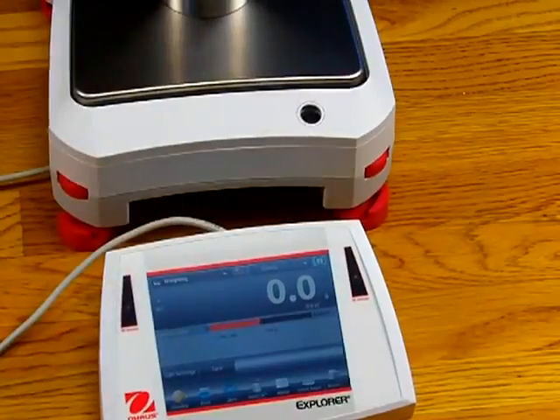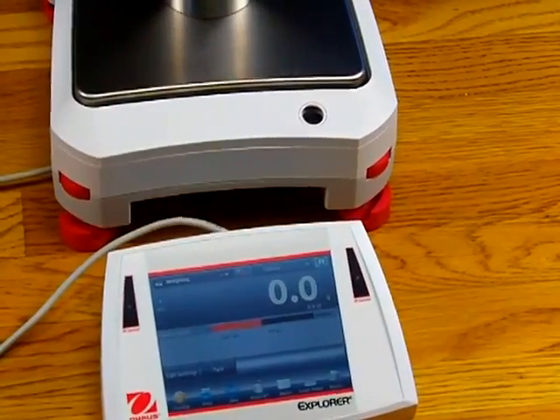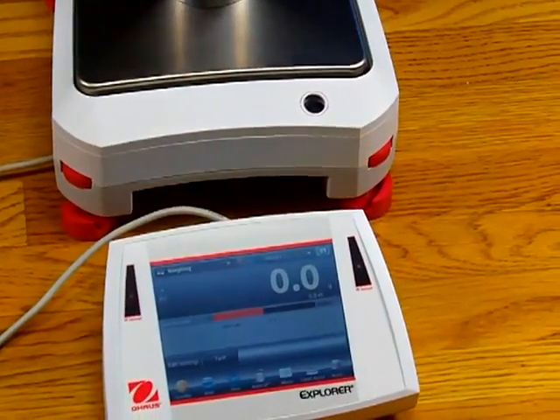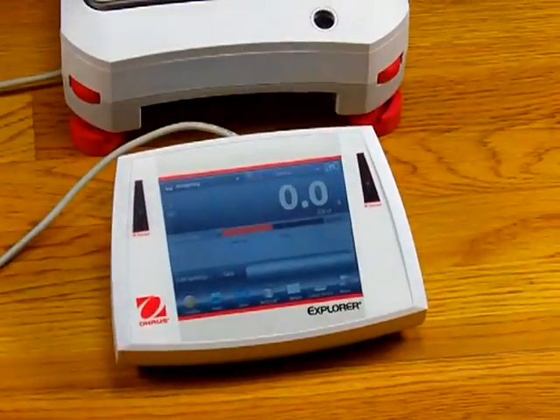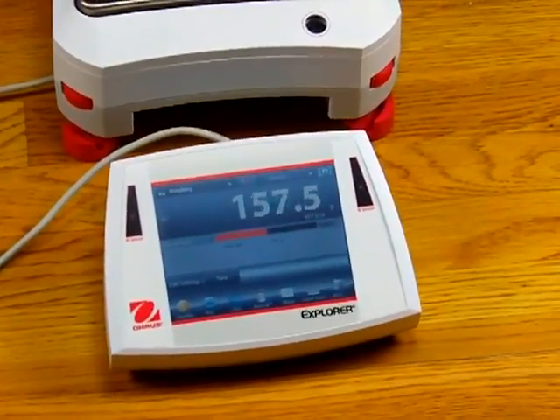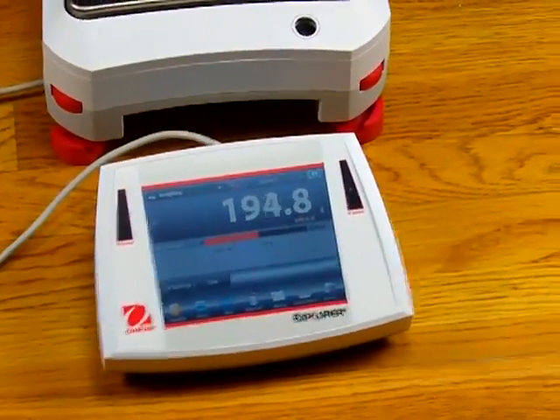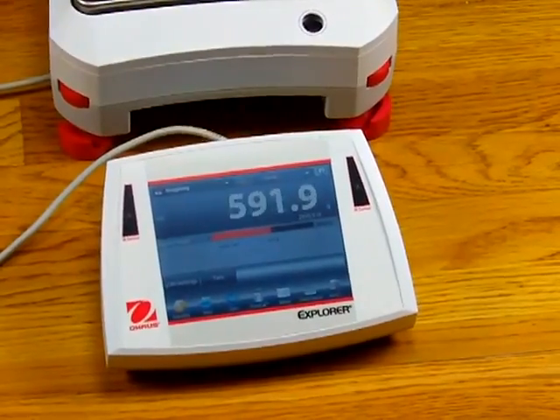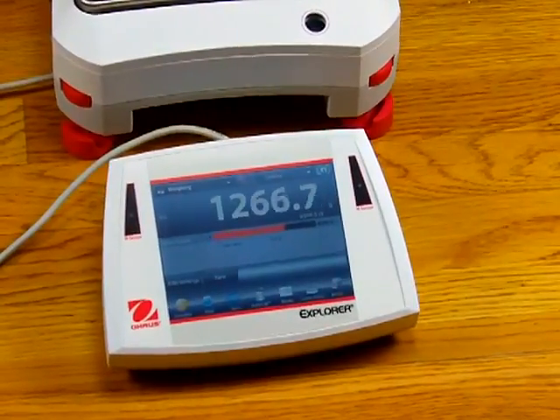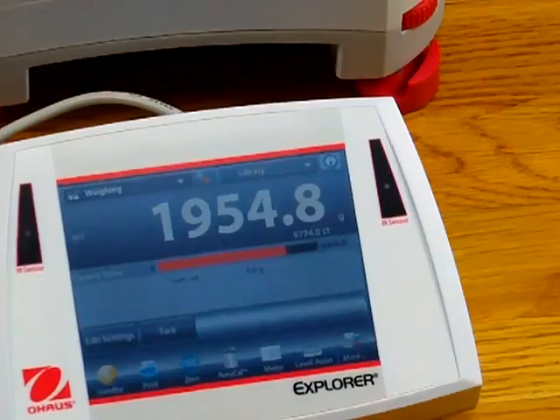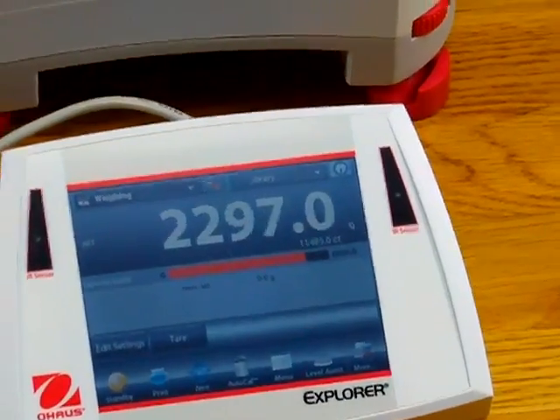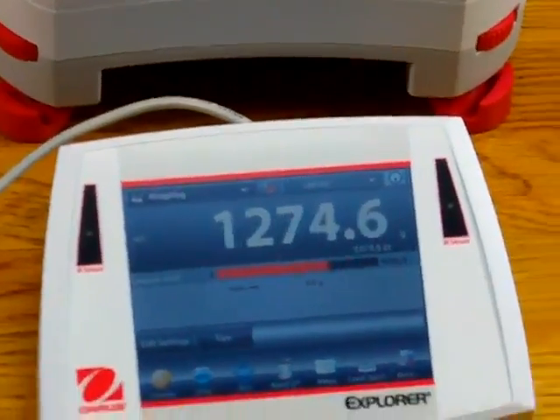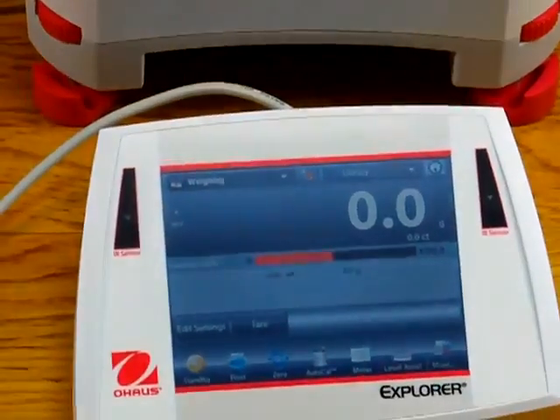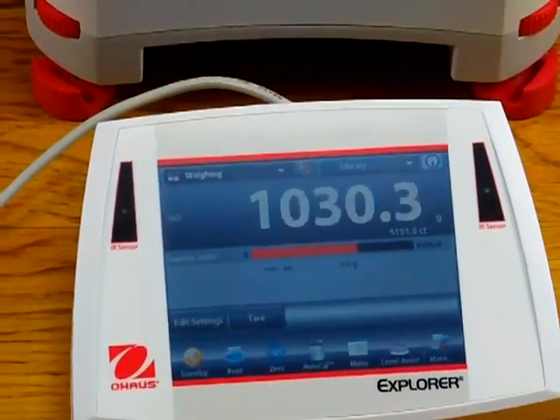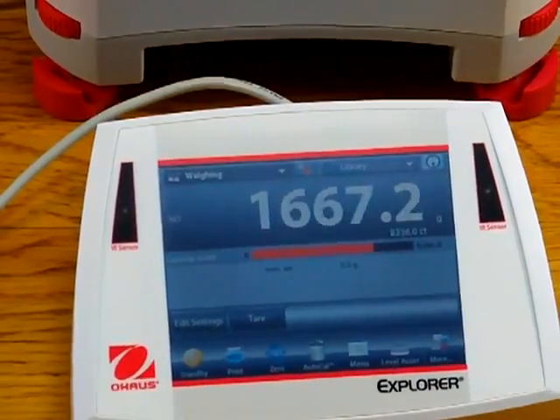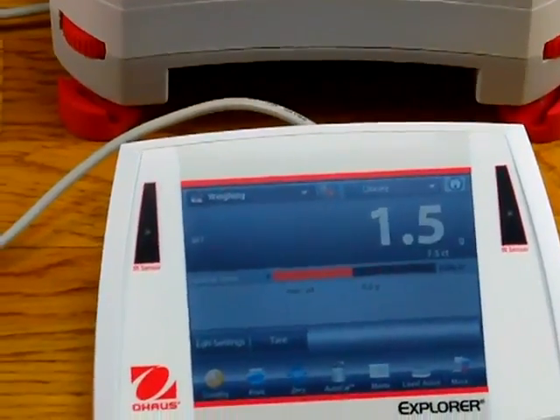This fill guide shows you how much capacity has been used on the balance. Again, this particular balance has 6,200 grams capacity. So if I add some additional weight, you'll see that display guide go up, up, up, up. I can put on here 6,200 grams or so, and you can see this fill guide in red as it drops, giving the operator an idea of how much of the weighing capacity has been used.